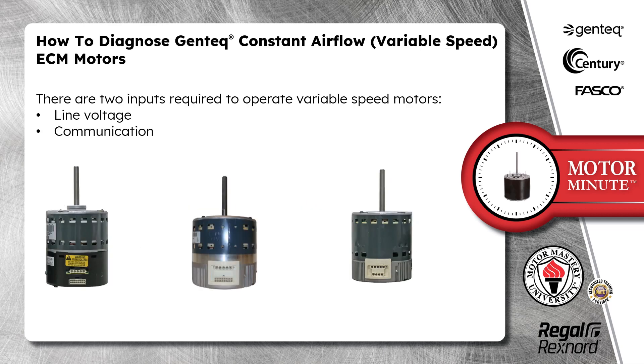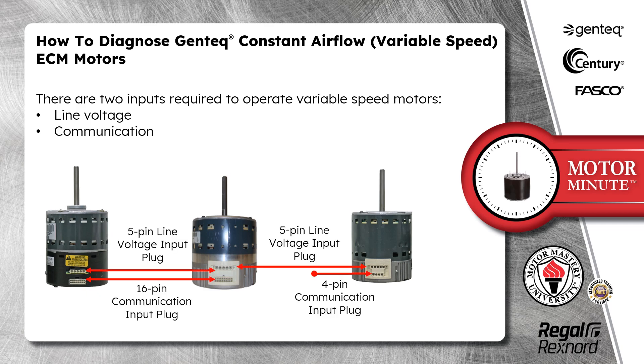There are two inputs required to operate Genteq variable speed motors: line voltage and communication. The line voltage connection is the five-pin plug. The communication input is either a 16-pin or 4-pin, depending on the model of the motor.